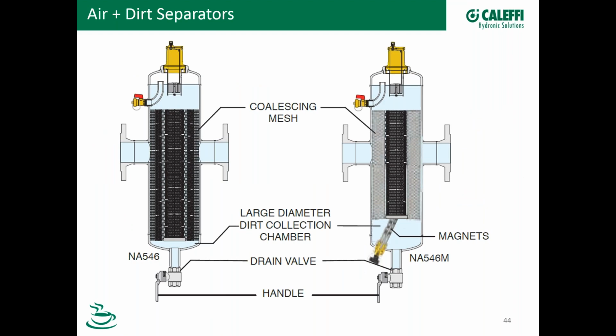Here's what the air plus dirt separators look like on the inside on the commercial models. So here, again, we have the lower housing doing the dirt removal, and the upper section with the long stroke air vent and the side port and this coalescing media filling up the whole entire section of the body. This one on the right just happens to be an image of the magnetic, the NA546M with magnet. So this has magnetic, air removal, and dirt removal all in one device.